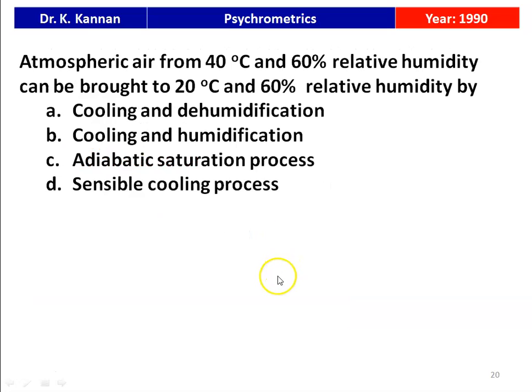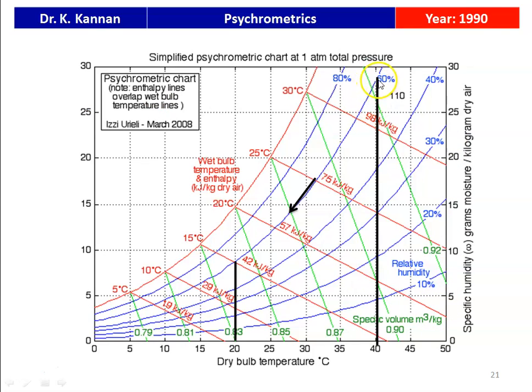The next question is from the 1990 question paper. Atmospheric air at 40°C and 60 percent relative humidity can be brought to 20°C and 60 percent relative humidity by: cooling and dehumidification, cooling and humidification, adiabatic saturation process, or sensible cooling process? The answer is cooling and dehumidification. From the psychrometric chart, traveling along the 60 percent relative humidity line from 40°C to 20°C represents the cooling dehumidification process.